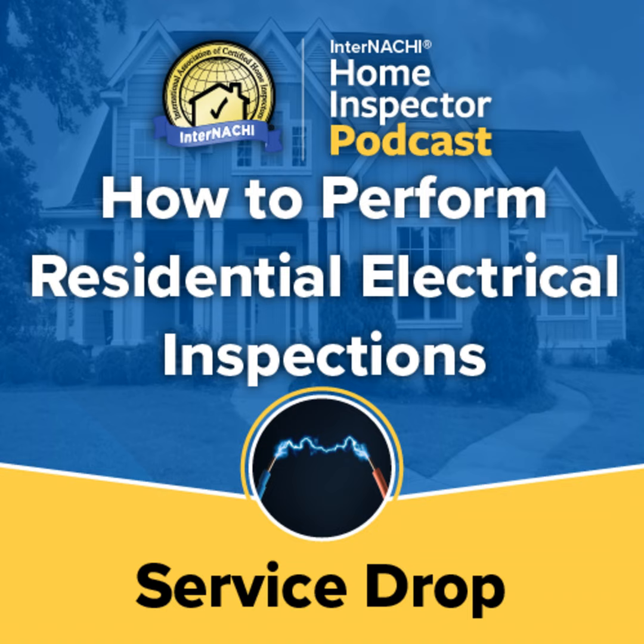Overhead service. In many residential areas and practically all rural locations, the electrical supply is delivered to the property via overhead conductors strung on wooden utility poles. The high voltage lines connect directly to the property through a transformer delivering main power. While the service overhead belongs to the utility company, the inspector should still evaluate it, particularly to determine the available voltage, its clearances, and any mechanical damage. When the service drop is located above the eaves, the service mast or riser is run through the eaves.